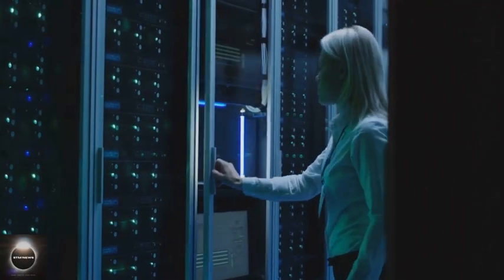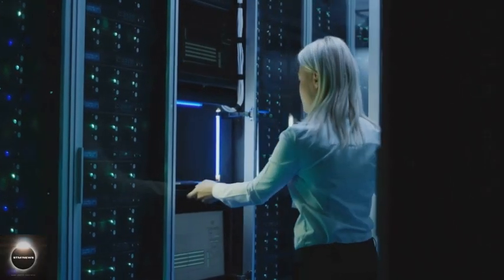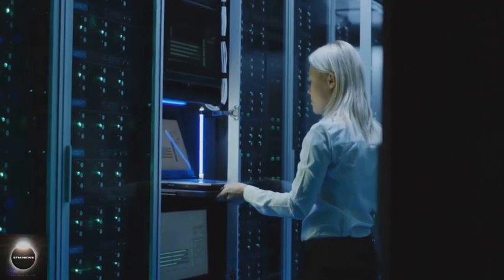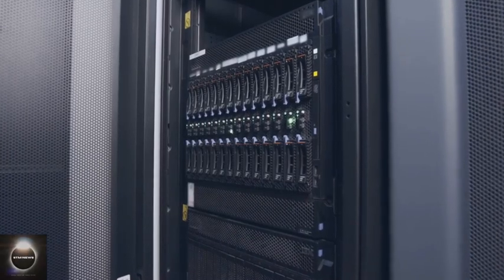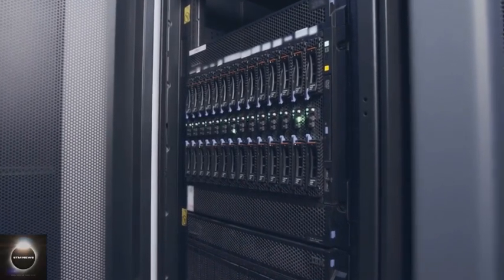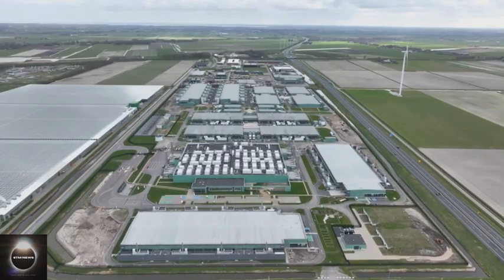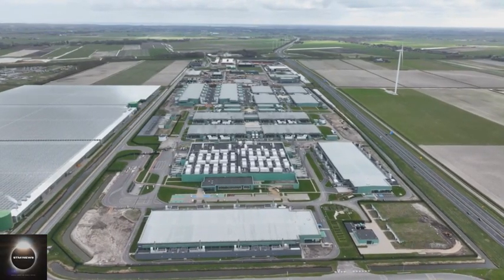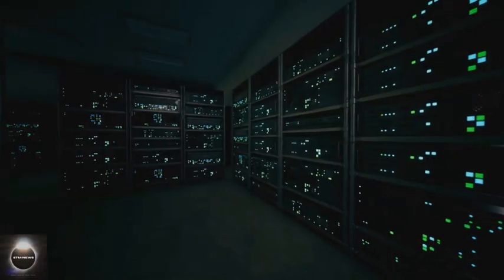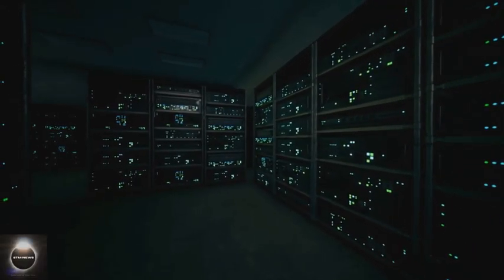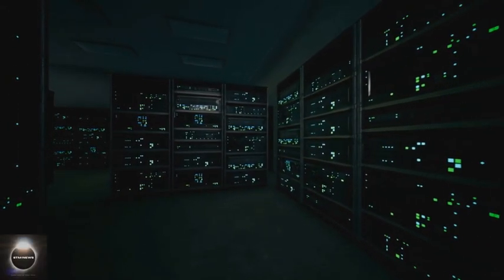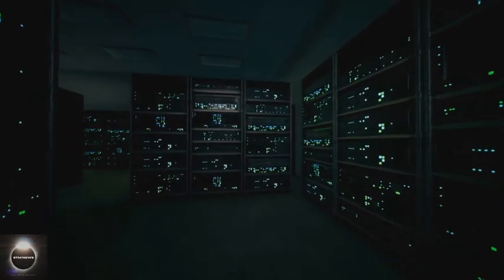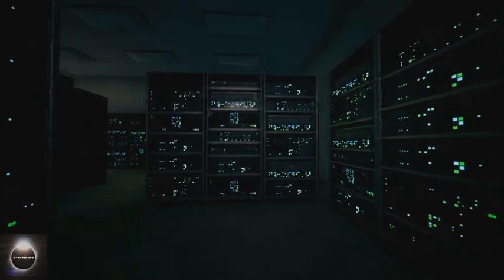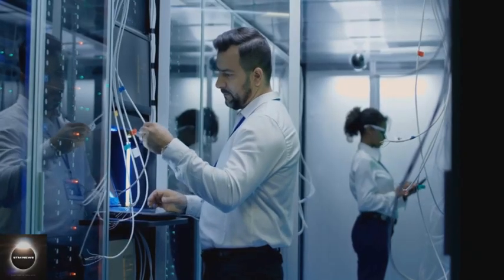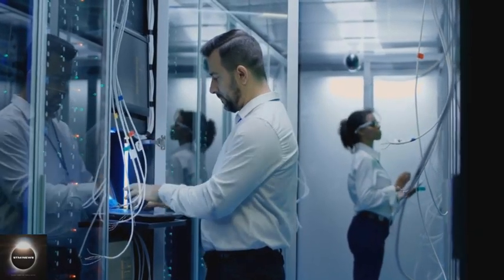Containment physically separates aisles, with curtains, clear panels, or rigid enclosures. Cold aisle encloses supply air. Hot aisle captures exhaust back to units. No mixing means higher set points and lower fan power, saving energy. Details matter. Blanking panels, brush grommets, tight doors, seal every leak to preserve pressure and target the air to server intakes. Disciplined airflow management is the hallmark of an energy-efficient data center.